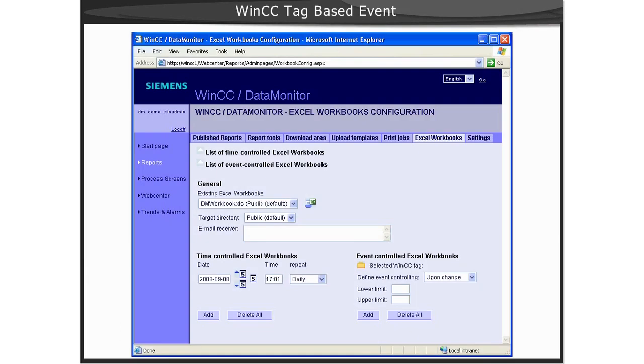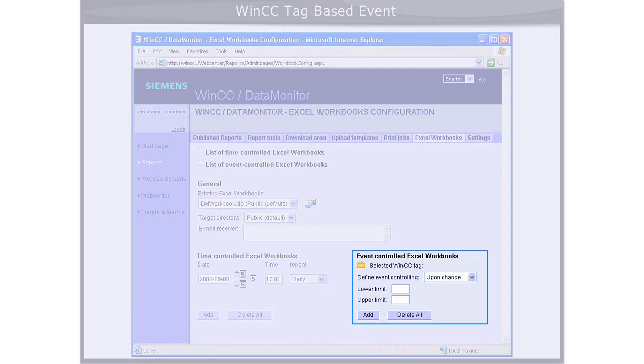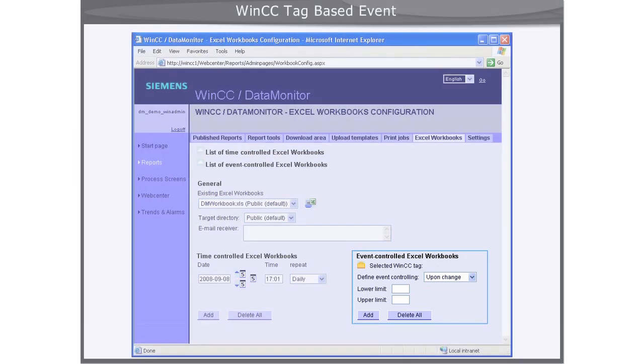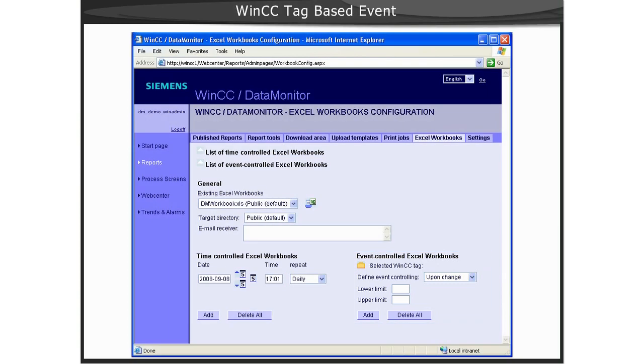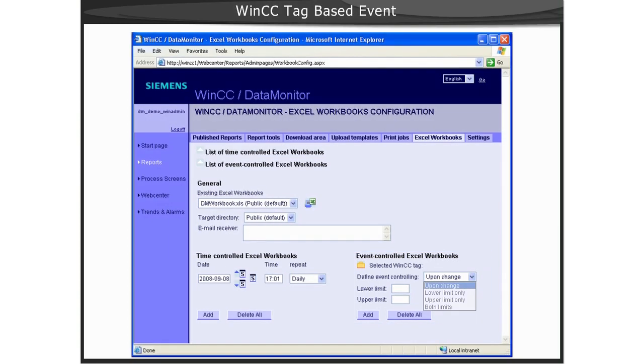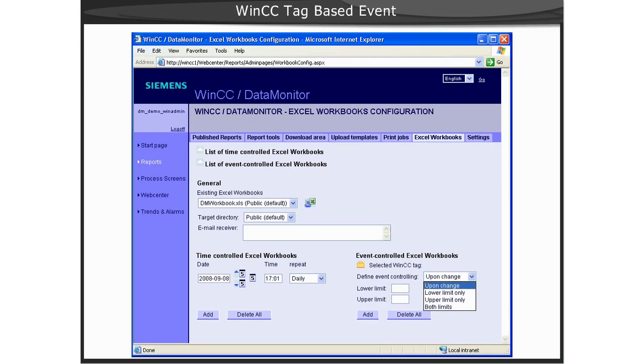If you choose to select a WinCC tag-based event, this event can be based upon the tag value changing, which would be an appropriate type for, say, a bit. Or you can select a lower or upper limit, or both limits as the event.